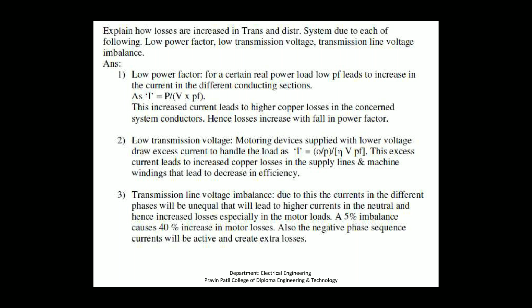Due to this, the current in the different phases will be unequal, which will lead to higher current in the neutral, hence increased losses, especially in the motor load. A 5% imbalance causes a 40% increase in motor losses. Also, the negative phase sequence currents will be active and create extra losses.